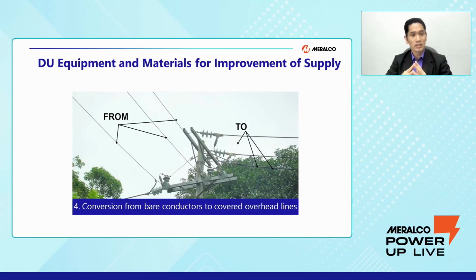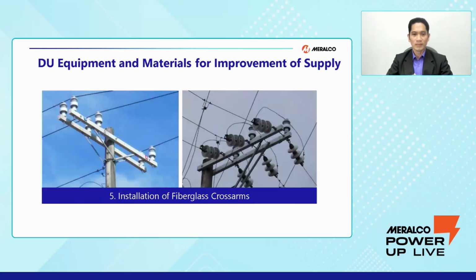And as well as conversion from bare conductors to covered overhead lines. In these coming years, Meralco will aggressively convert the bare overhead lines to covered overhead lines to address the transient faults due to trees and vegetation, and some animals or other activities like renovations and construction that will have temporary or transient contact with the Meralco lines. And as well as installation of fiberglass cross arms. This fiberglass cross arm will prevent the line to ground fault that might occur when animals, such as birds resting on the cross arm of our poles, make contact between the lines and the steel cross arm. Thus, it's a good investment to replace the steel cross arm with fiberglass cross arms.